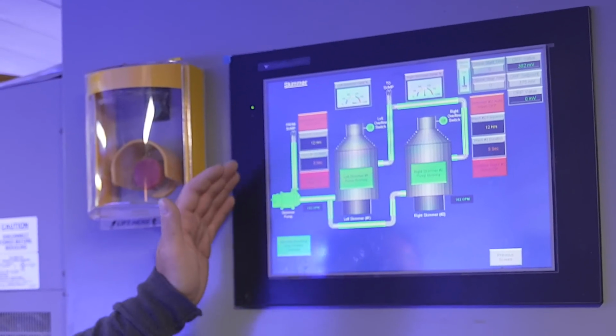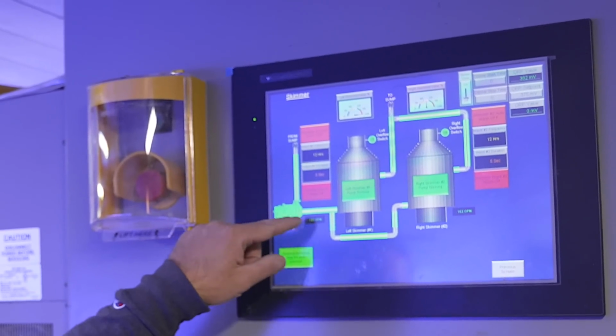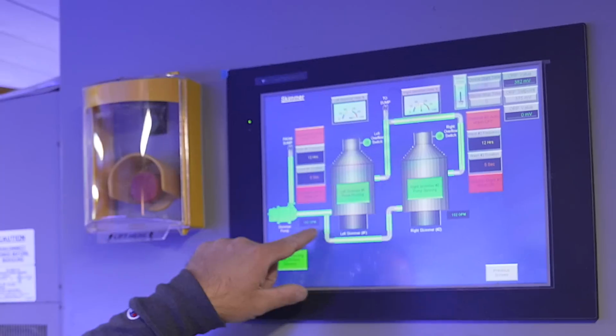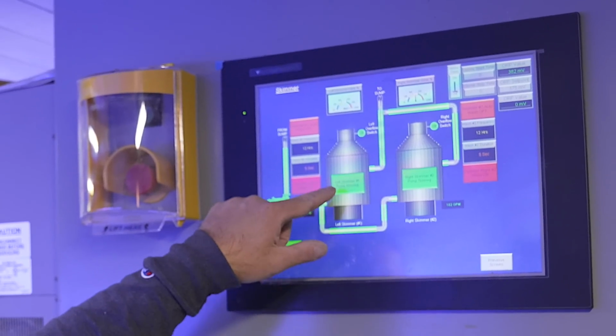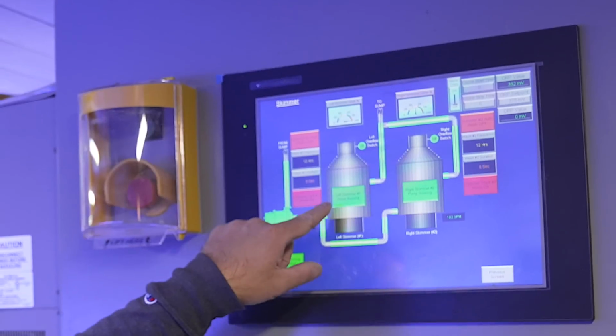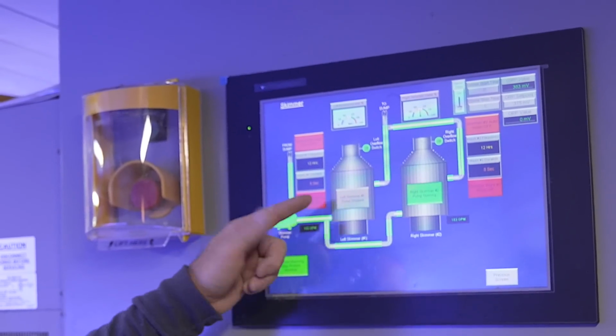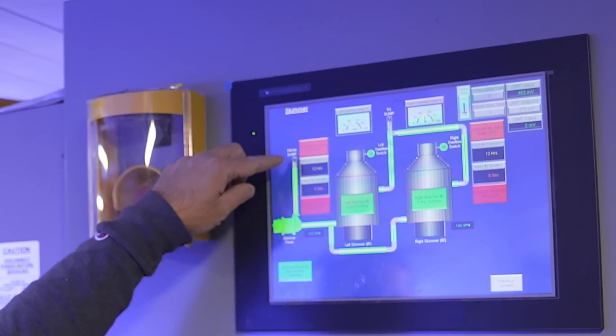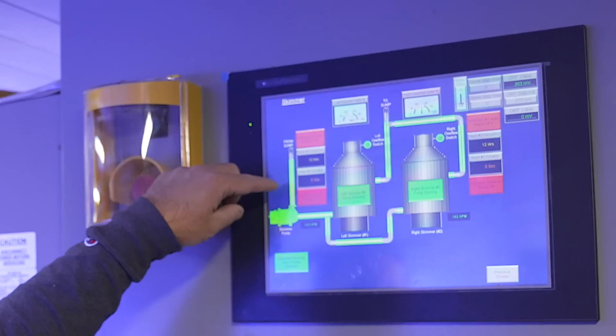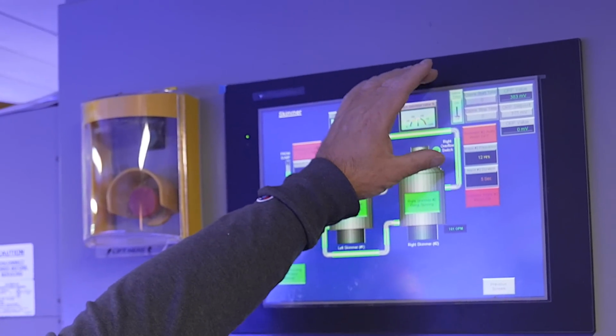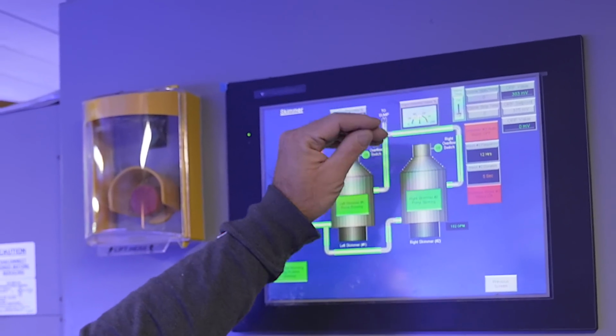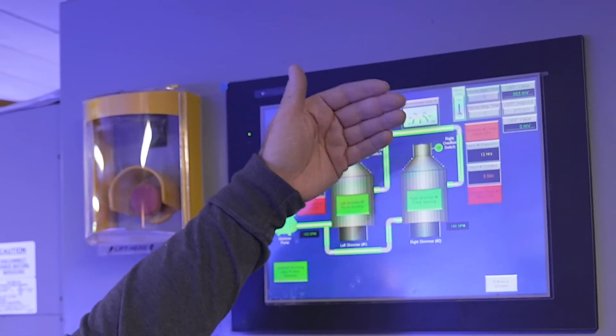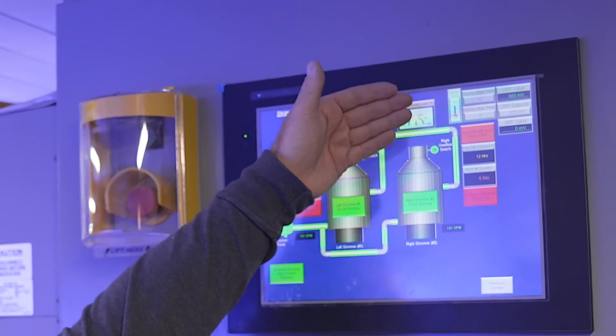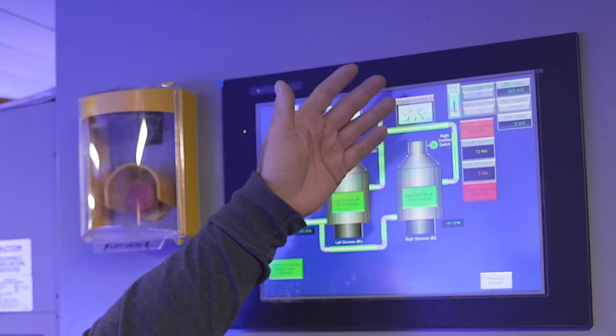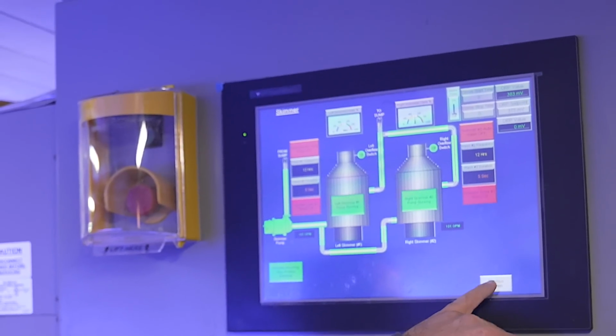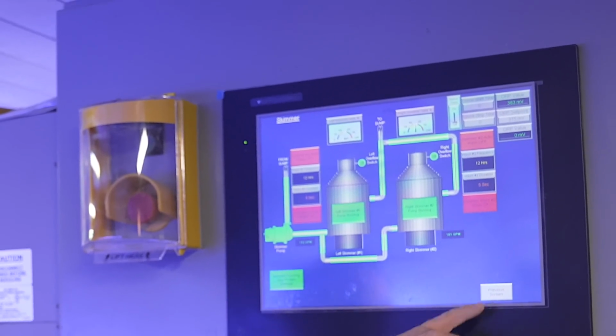On the skimmer here, we have the main pump that's feeding the skimmers, each one running 100 gallons a minute now. Their individual needle wheel pumps are on. We have the ability to shut those on and off. We have our washdown timers and duration of the washdown, as well as our ozone set point and levels. And if we wanted to run that ozone on a specific time frame, we could do that too. If we didn't want to run it during the day or at night, we could adjust it that way as well. But now we're just relating it to ORP.